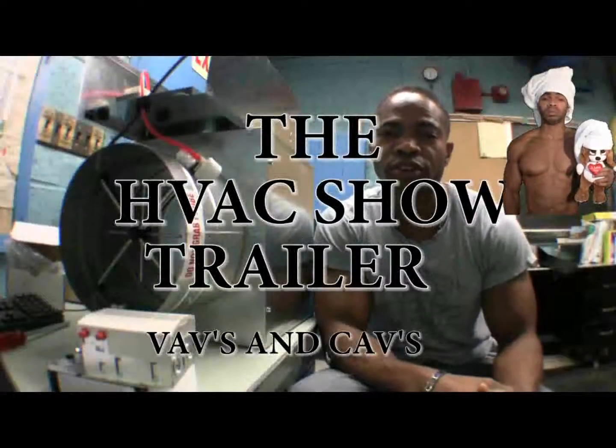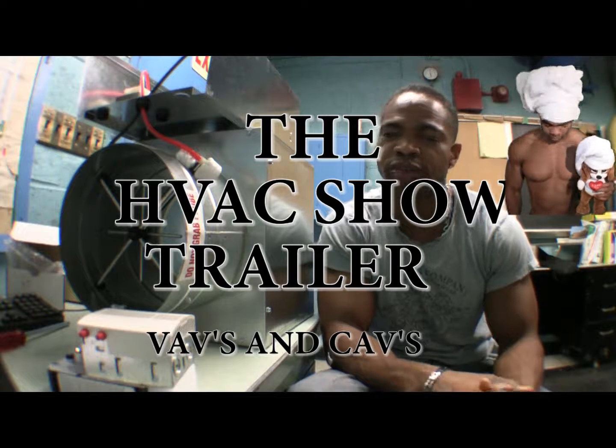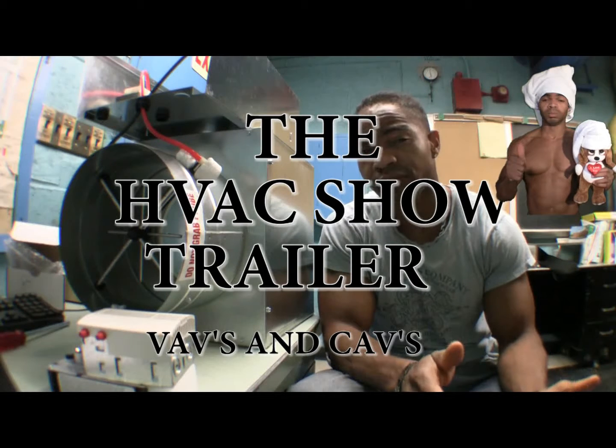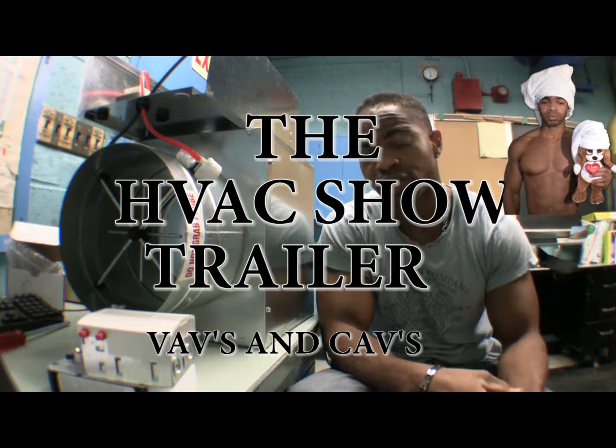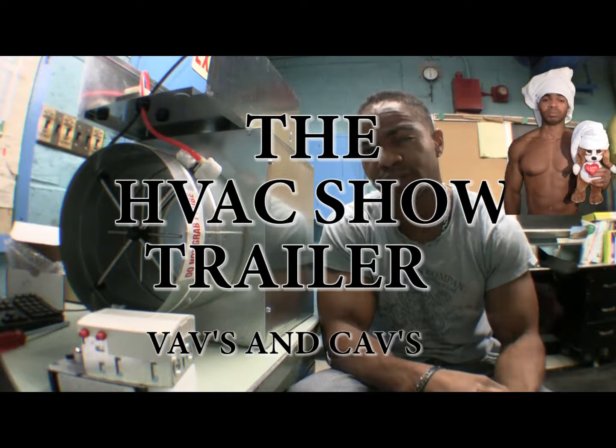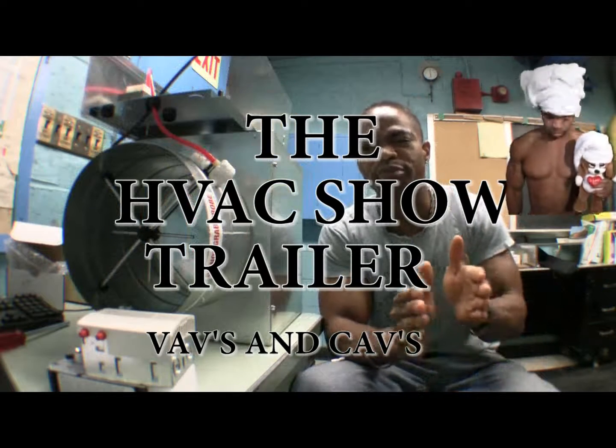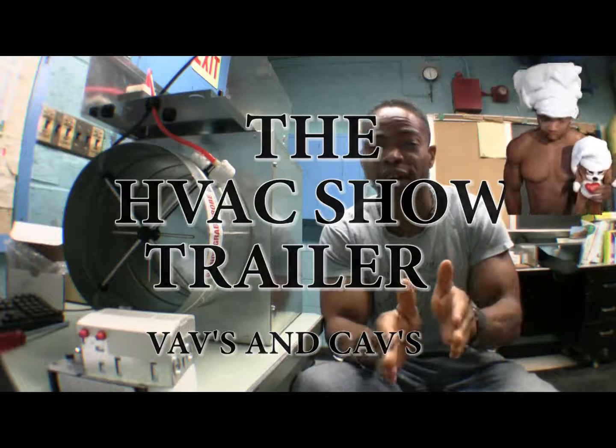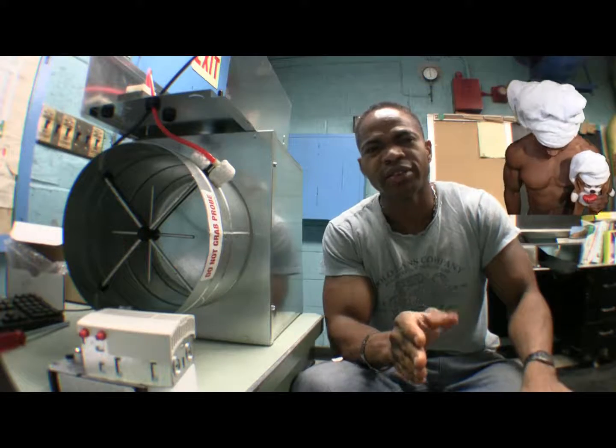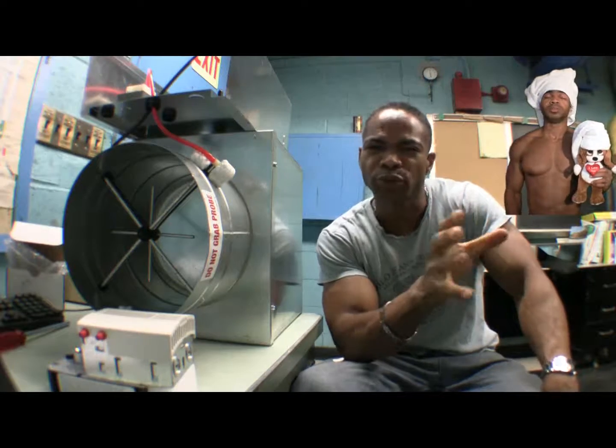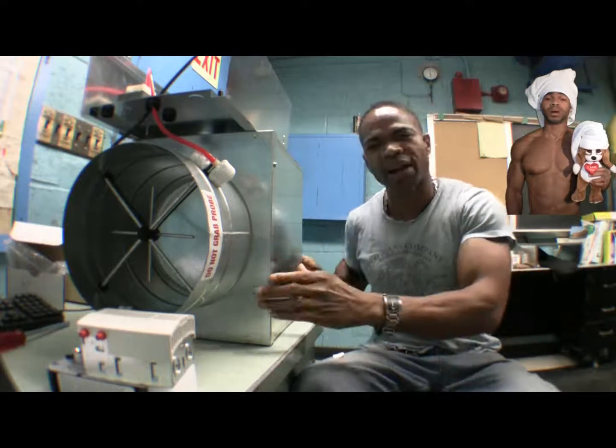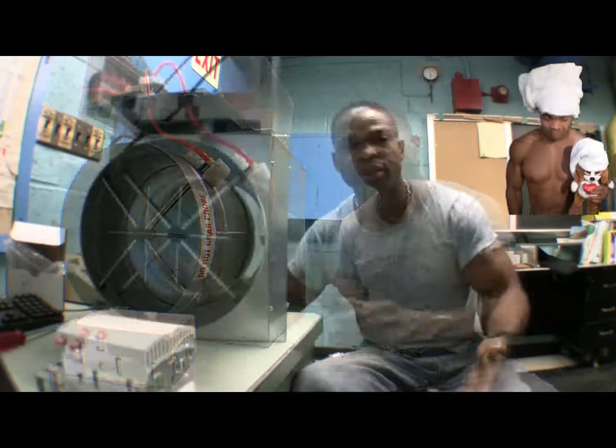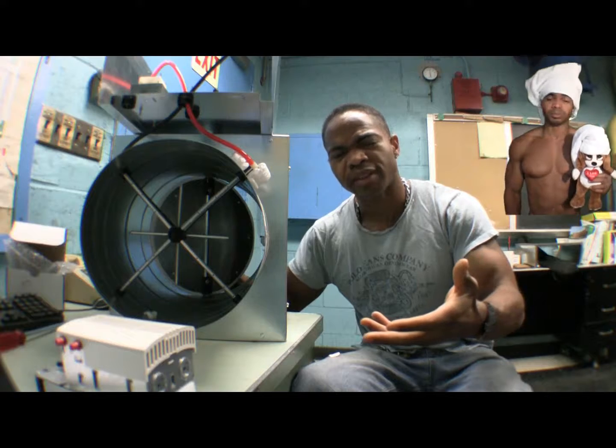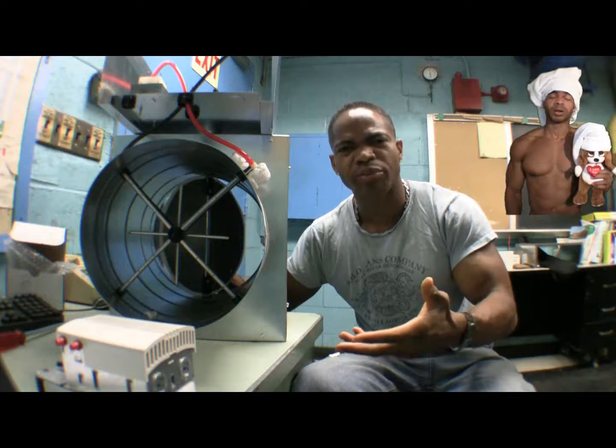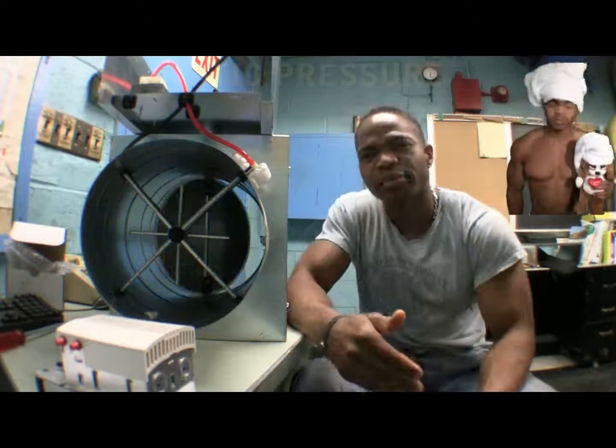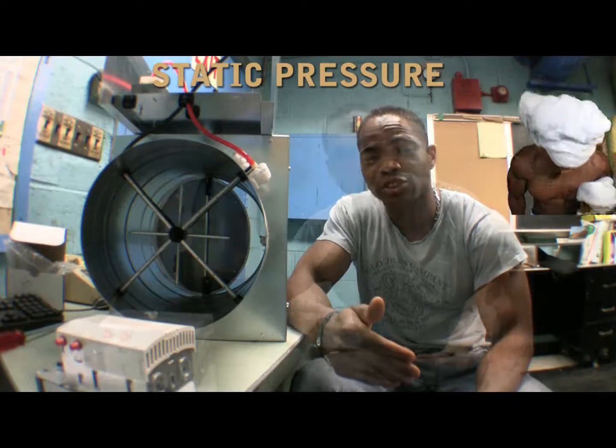On larger air conditioning units, you use a VAV or CAV box, a variable volume box or constant volume box, in conjunction with the unit. For a room, or for at least two or three rooms, you'll put a box like this, and as the room warms up, the box will begin to open up to send more air into the room.